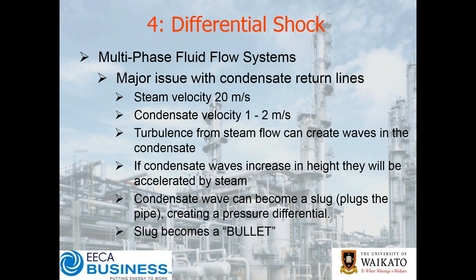The fourth form of water hammer is multi-phase fluid flow — or differential shock. This is a major issue with condensate return lines. We'll have a steam velocity of 20 metres a second or less if you've listened. Some of you might have inherited a system that's a little undersized, or perhaps the condensate line was correctly sized but then another process engineer came along with a plant upgrade and added extra capacity — but everyone ticked the box and thought the condensate system's fine, leave it. Then over time the load on that system crept up.